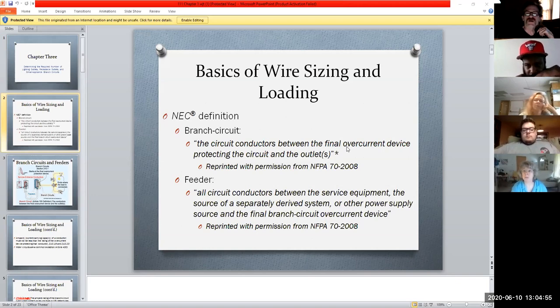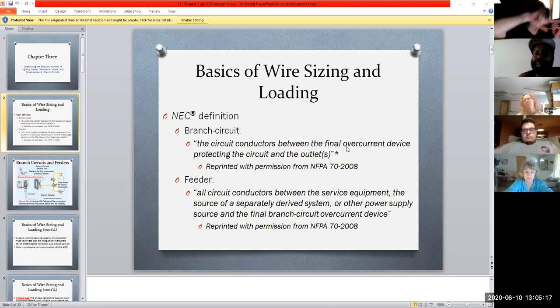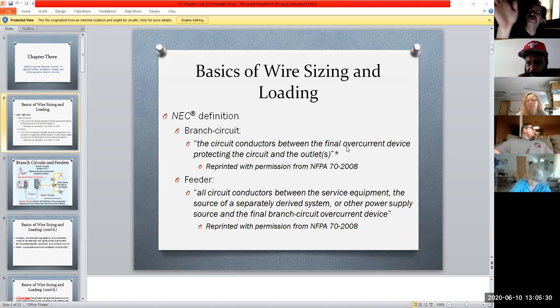And then we look at something called feeders. Now, a feeder is considered basically all circuit conductors, and by conductors, usually we mean the wiring involved, because that's what the current is going to travel on, between the service equipment, the source, and any other power supply source in that branch. So anything within that loop, as I feed out and then come back, because current always has to have a path to go. That would be considered the feeder circuit, because I'm feeding off of that.